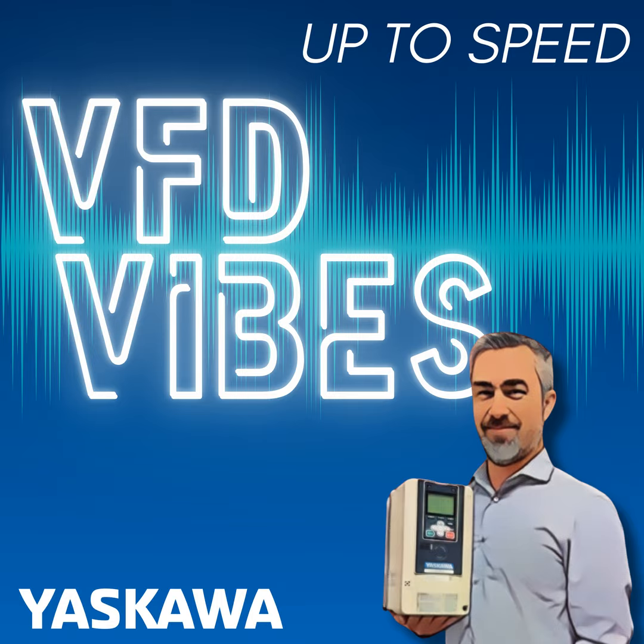If you go out and measure the 3-phase, you don't get 480, 480, and 480. More than likely, you get 480, 480, and 472 or something like that. Oftentimes the phase that's missing the transformer will be a little bit low, but the impedances will be different. And so running from an open delta supply, you often have to derate the drive or add a line reactor.